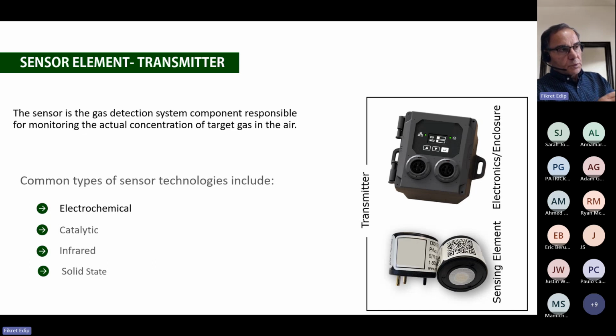To talk specifically about each one of those is beyond the scope of this course, because it would take much longer to discuss. However, one thing to take away from this: infrared is the Cadillac version of the sensors. It's a lot of time used, why? Because it's accurate and it takes much longer. It uses a light beam in detecting the particles, the leaked particles. Solid state sensors are much cheaper, for lack of a better word.